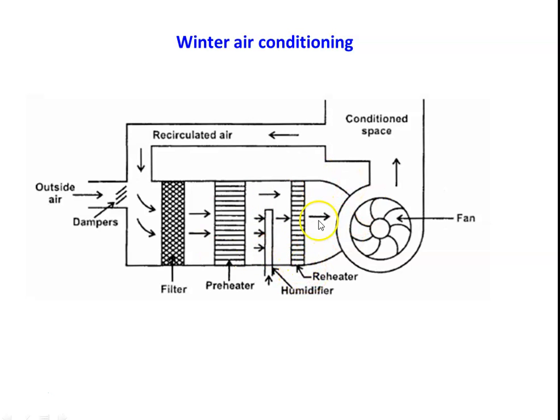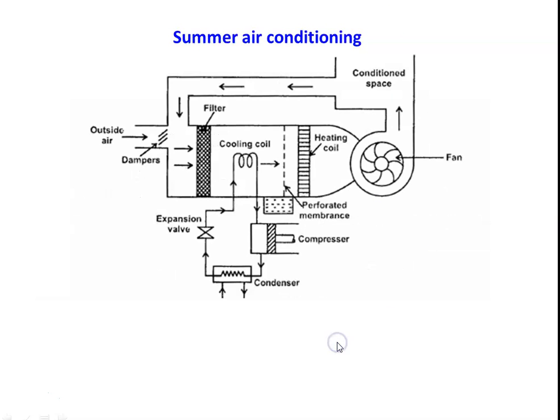And this is the conditioned air, and using the fan, it is circulated to the air conditioned space. So this is used in the winter air conditioner. And the summer air conditioner, so what is the operation required? Cooling and dehumidification. So look at the various components here. First we have a filter, we have the damper. And here for the cooling and dehumidification, we have a refrigeration circuit.